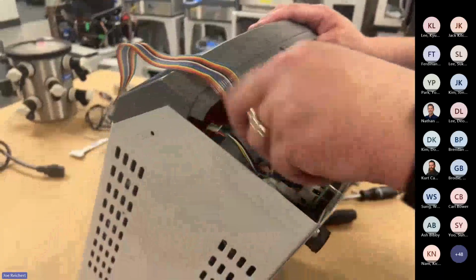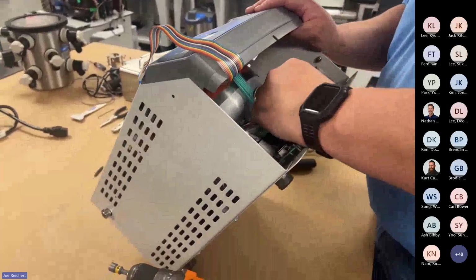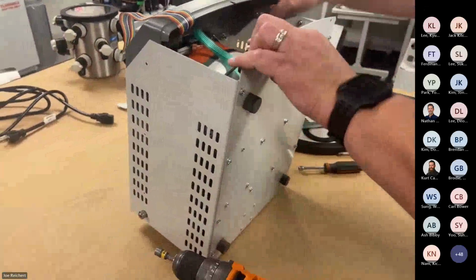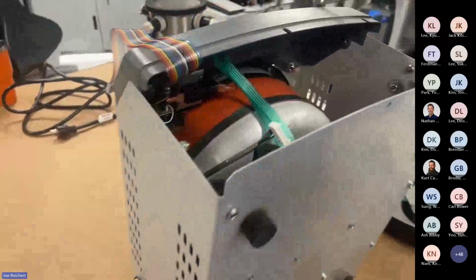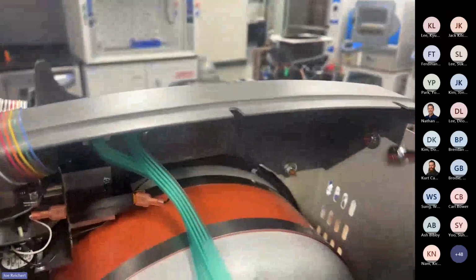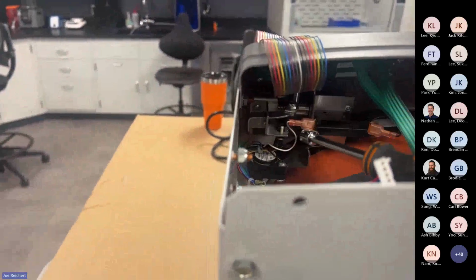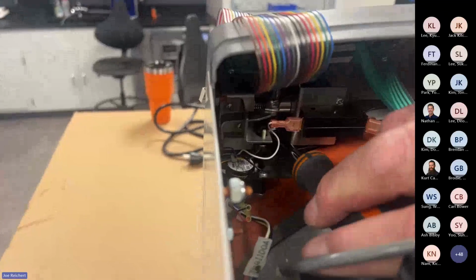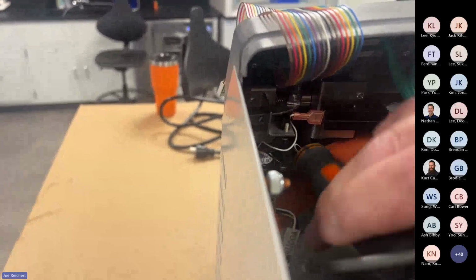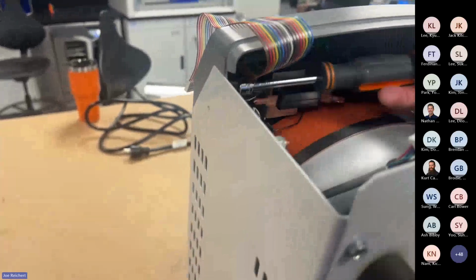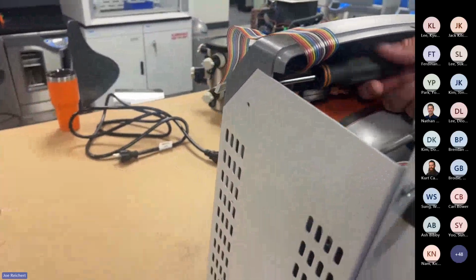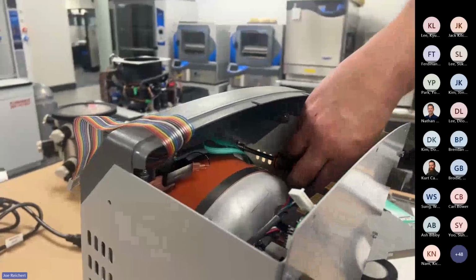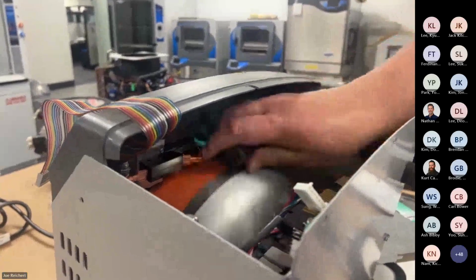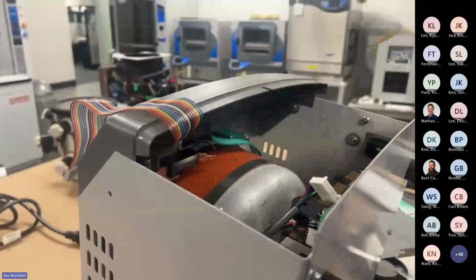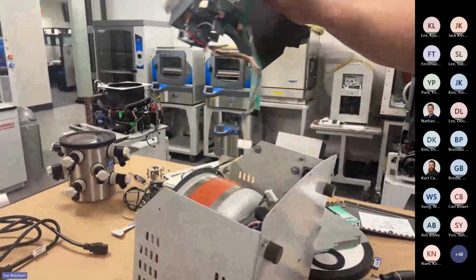Inside the unit, I need to undo my wires a little bit here from the PC board. There are a couple more 3/8 nuts that hold the control panel on. They're up here in the top, one here on the side. On this side, there's also one here, and then there's another one that's up above where the cooling fan is. I'll grab that as I can see it. And again, just loosen, do not remove. You can remove them, but that's just something else to remember where they go. Since the holes are slotted, it slides right off. And here comes your control panel.